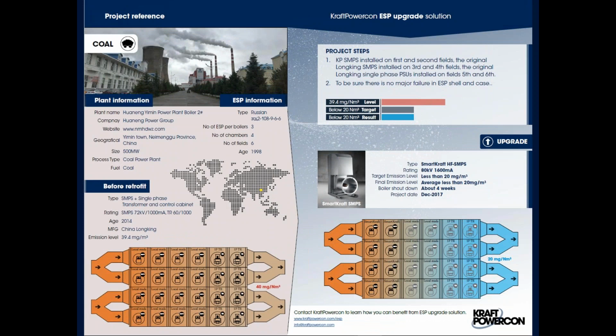This is another case, a larger coal-fired power plant in China, 500 megawatts. As you can see, the precipitator is, let's say, lightly compliant. In China and other markets you'll have different tiers of TR sets, like in India and China, and this is just the reality. I don't want to get into competitors, but you have two tiers of suppliers in both these areas. One tier where the TR is just good enough—they put it on, it puts high voltage in the field, but it doesn't really meet the limits and ratings of the TR set. It just needs to put some voltage and allow some current into the field, and reliability isn't a big concern because they just put it on and operate it.